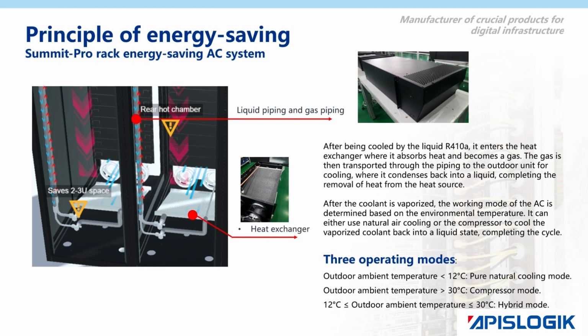Once the refrigerant is vaporized, the rack-mounted energy-saving air conditioning system determines its operating mode based on the ambient temperature. In lower ambient temperatures, it utilizes natural air cooling. In higher ambient temperatures, it employs a compressor to cool the vaporized refrigerant back into a liquid state, completing the cycle.